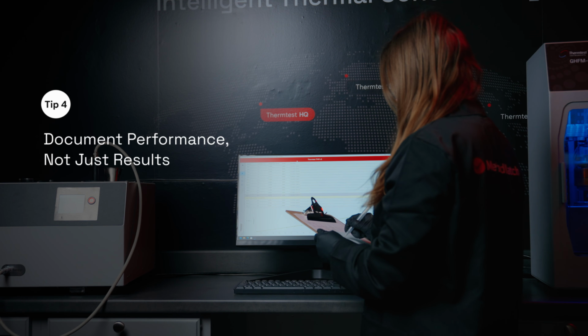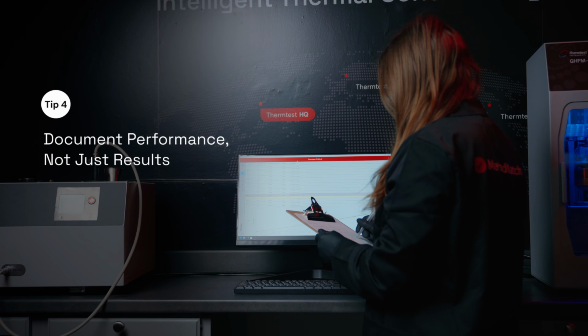Maintaining records of test conditions, verification results, software changes, and unusual observations makes it easier to track performance trends. This documentation provides valuable insight in troubleshooting and determining whether recalibration is necessary. Software and firmware updates can improve functionality, but they may also affect data processing. After any update, it's good practice to run a verification test using your reference material to confirm performance remains consistent.